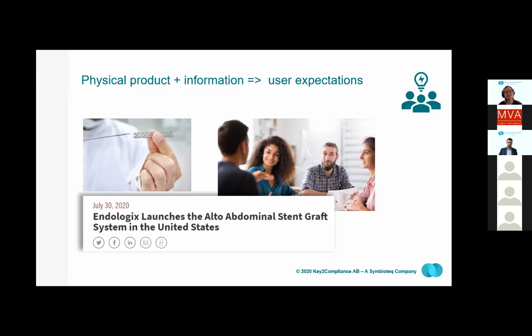The information together with the product is what creates the user expectations. And the user expectations relate to how the clinical performance will be perceived, what the risk profile will look like, and will in the end have an impact on the safety of the device. So it's really important to think that the combination of the device and the communication is what determines the user expectations, and the user expectations have a huge impact on the final safety and performance.